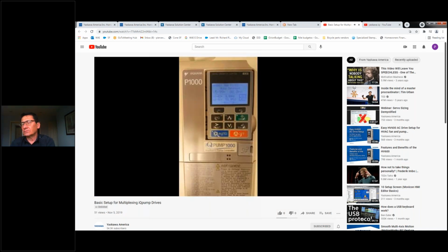In this video, I will be explaining how to program a 1000 series IQ pump drive for multiplex operation. The first step is to navigate to the parameter H501 in the programming menu. From the home screen, press the up arrow until the display reads Programming. Press Enter.